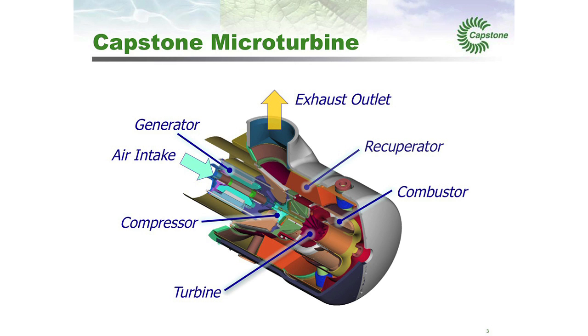So what's a microturbine? Really just a small gas turbine. We've done it in a unique way in that we've got the generator and a very simple compressor wheel and turbine wheel, all on one shaft — one moving part, we like to say — and that's all supported on air bearings. So you don't have to change the oil or dispose of the oil, which helps with maintenance and also the emissions benefit of the technology.